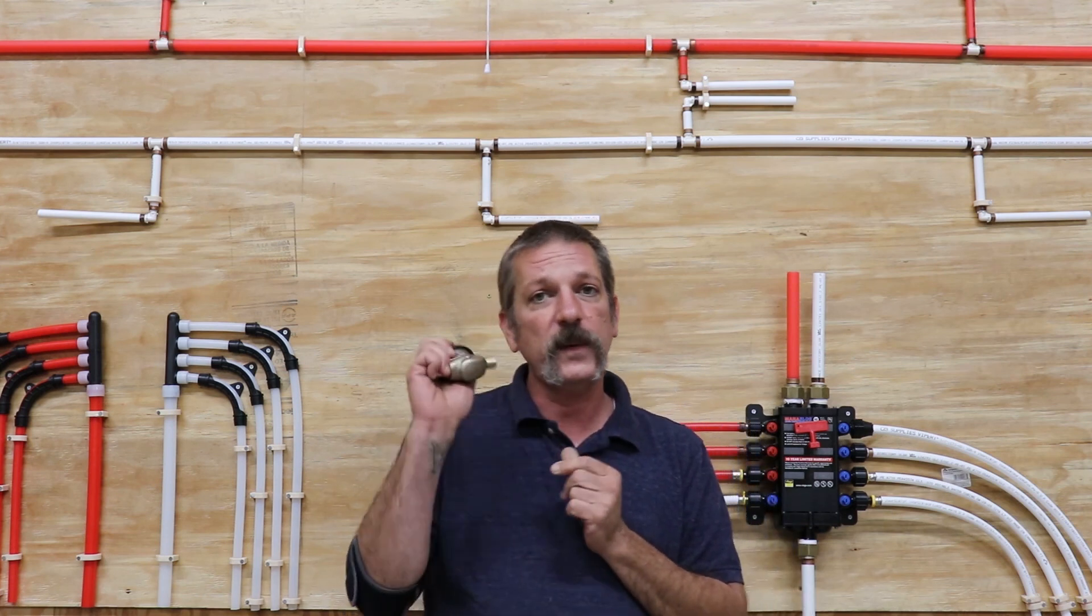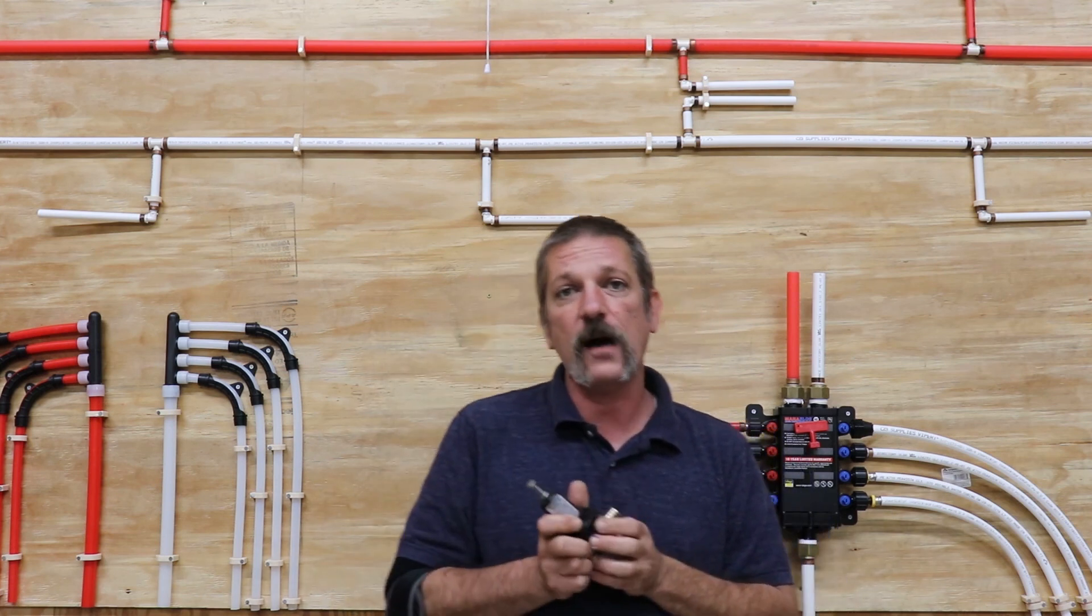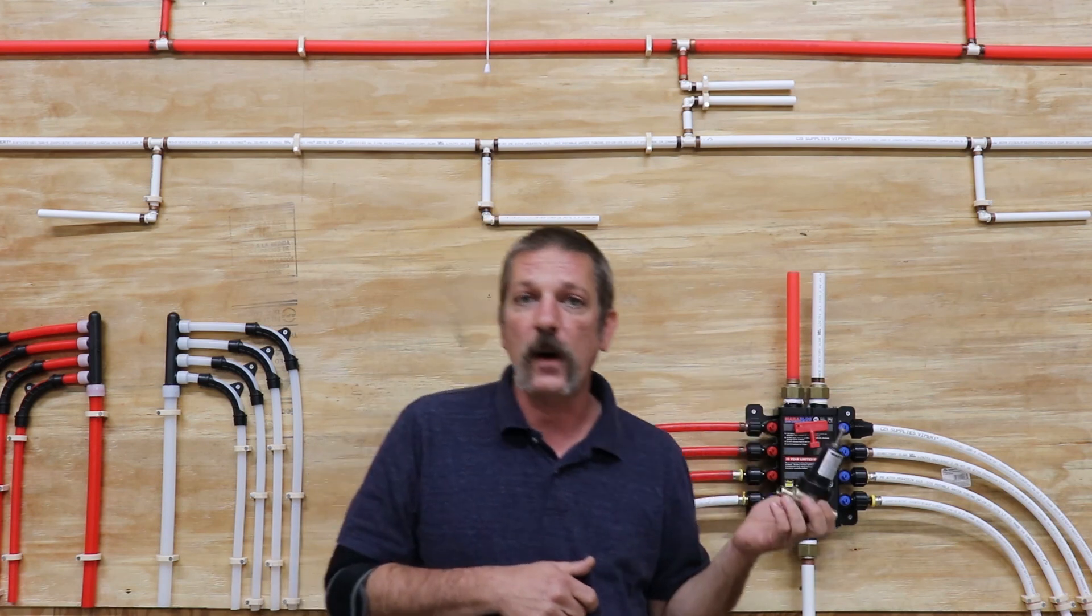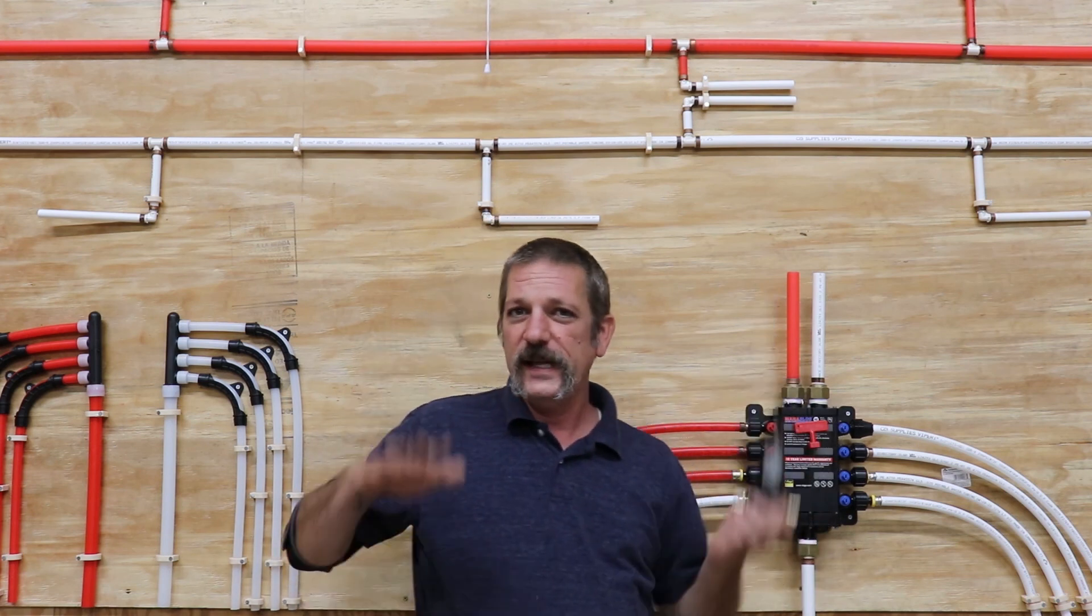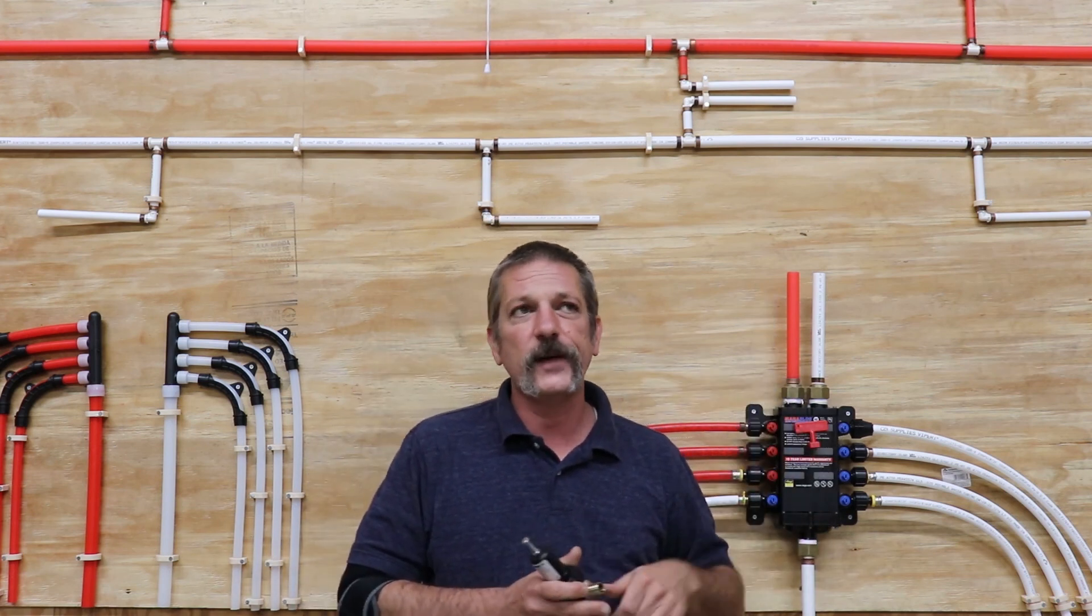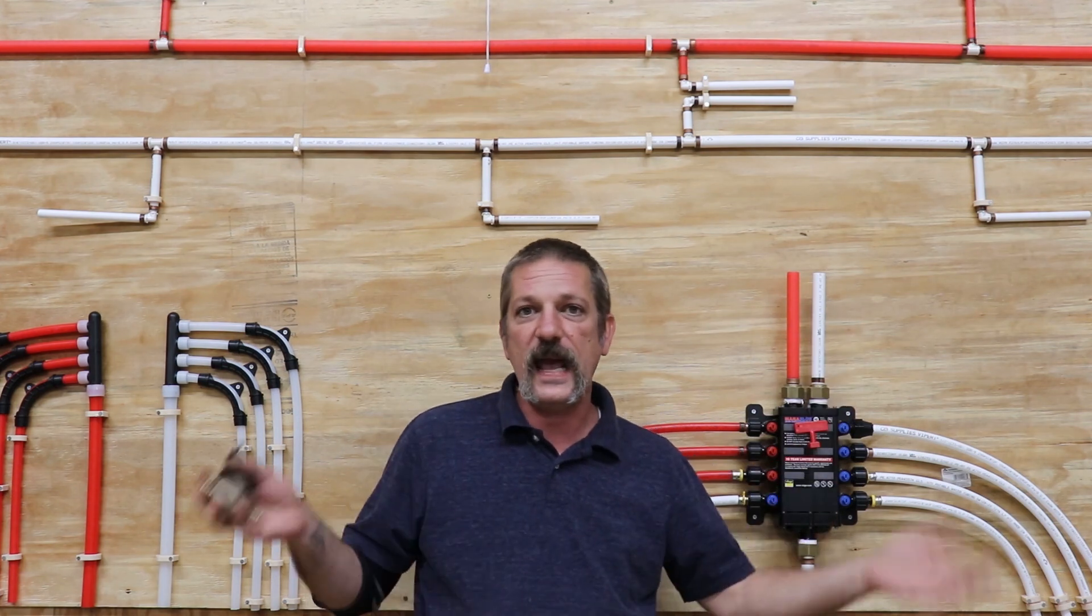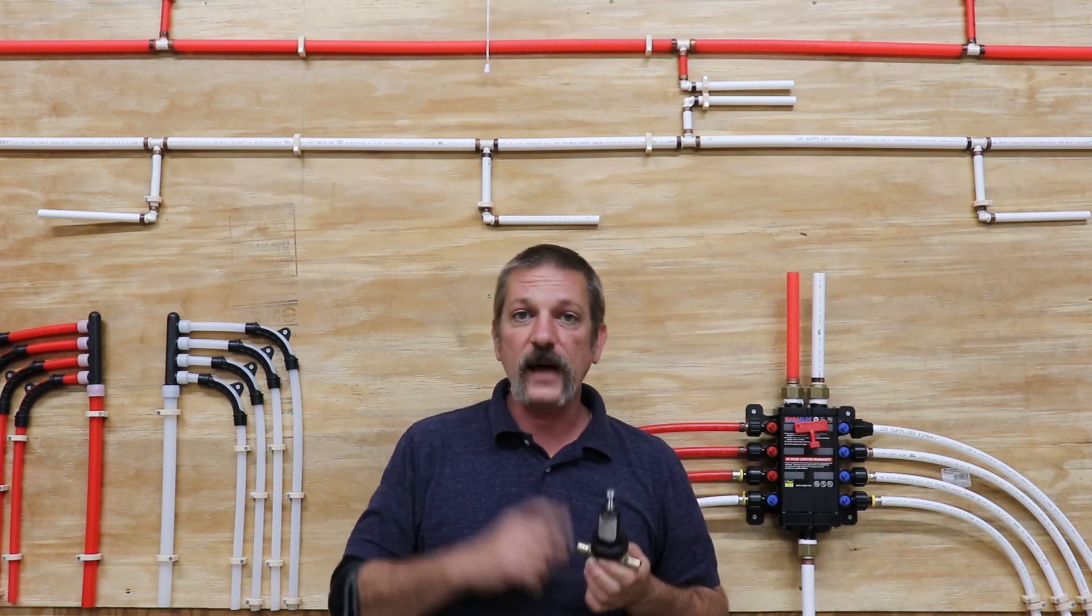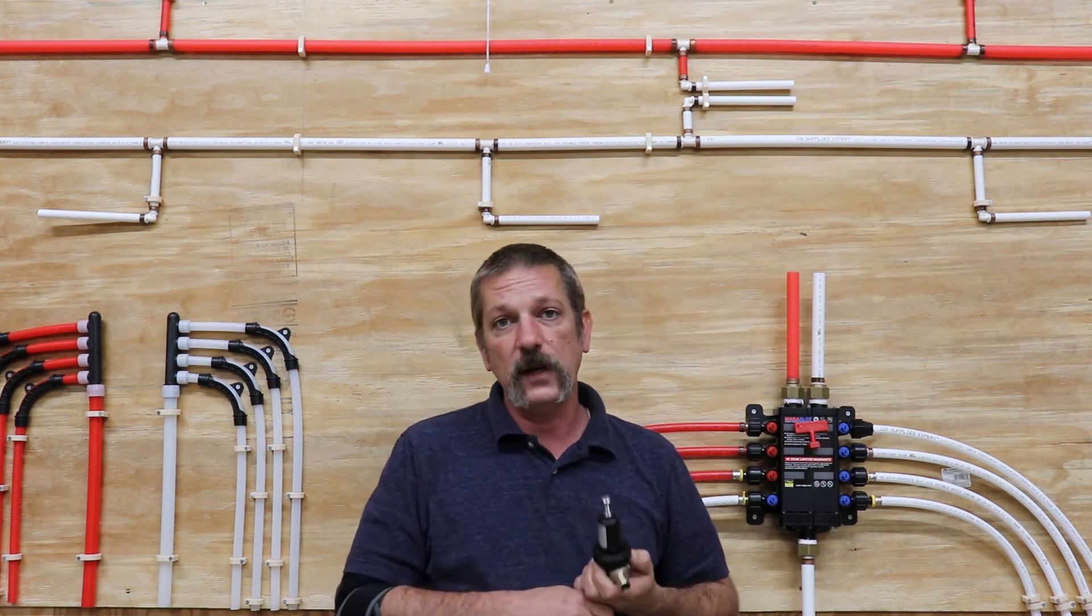The other thing, why this would be called a pressure regulating valve, say you've got a booster pump or something that's really varying in its pressures, say somewhere in between 60 and 80 psi. You can use this guy to hit that target of 75 psi because of the way the little valves and stuff in here work.